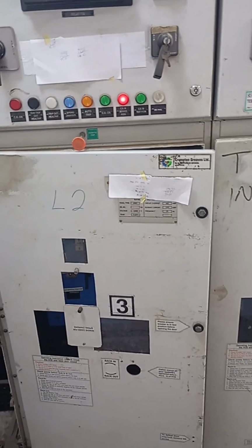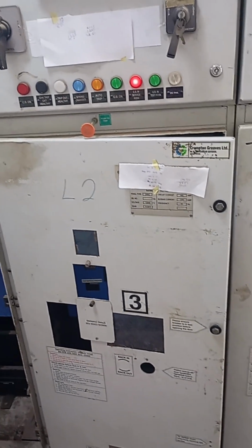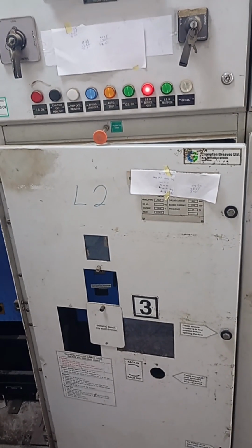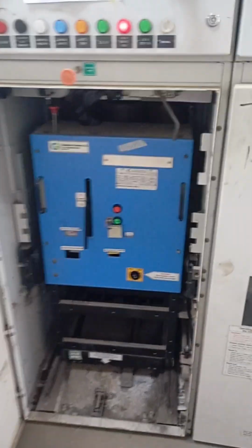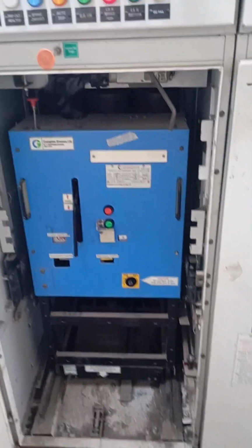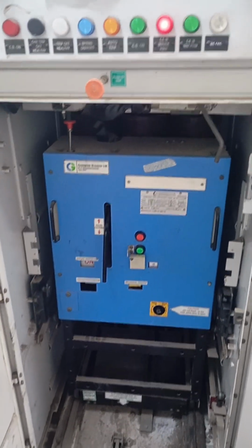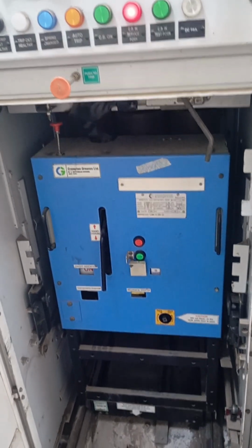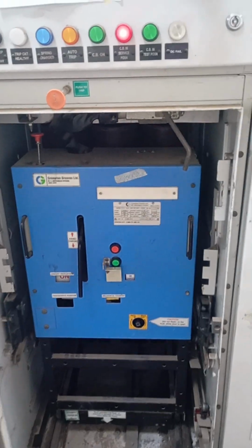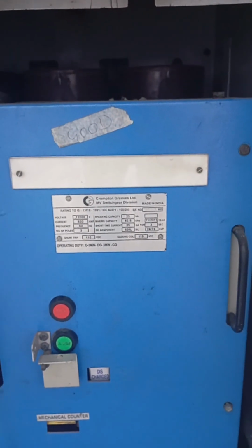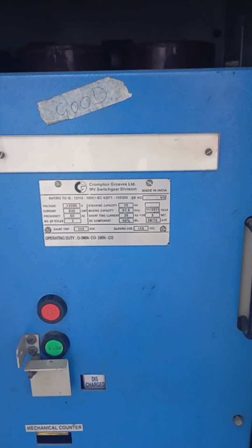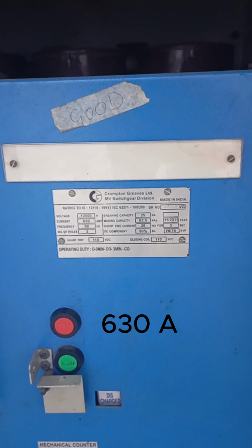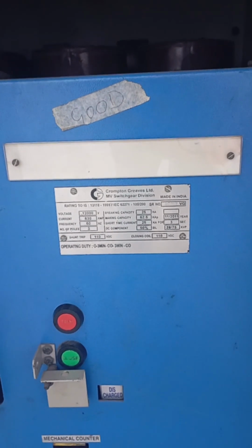The second compartment is the breaker compartment. I believe all of us know what a breaker is, but in power systems, this is what a breaker actually looks like. Do you see it? This breaker is different from the kind of breaker you are used to seeing outside, because this is a very heavy breaker. Let me show you the nameplate of the breaker so you can see its details. You see the voltage, 12,000 volts. You see the current, 630. You see the frequency. So you can know how big the breaker is.